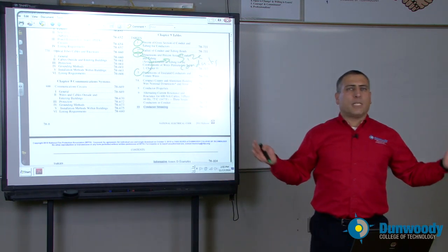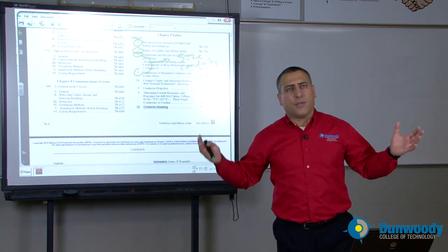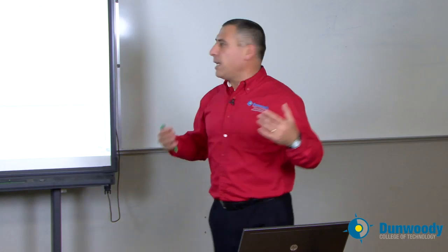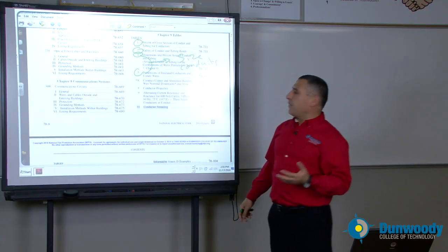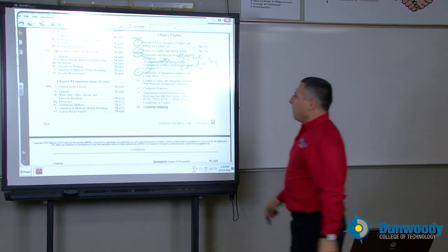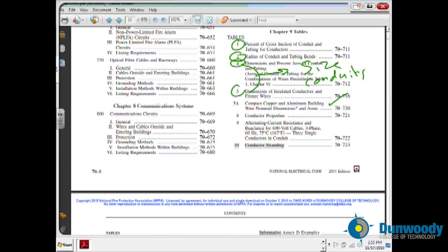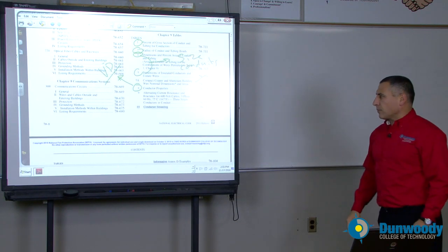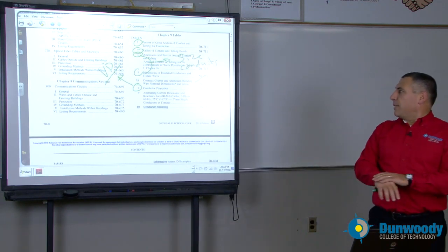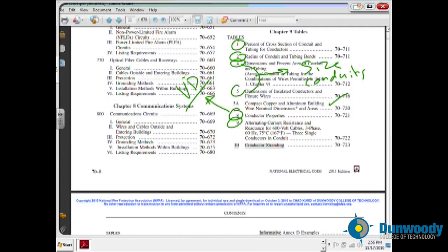For example, I can put 16 number 12 THHN conductors in a three-quarter inch EMT conduit. How do I know that? You're going to do a calculation if there are different sizes and different insulation, directly from Table 4 and Table 5. There's also information about compact conductors and specially designed conductors. Table 8 is very important for voltage drop. We use Table 8 and Table 9 for AC and DC voltage drop calculations to find the resistance and impedance of a circuit to size the conductor based on length.